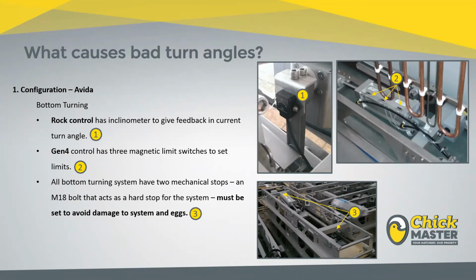If you've got a Gen 4 control, is denoted by picture 2 in the top right corner here, you're going to find yourself with 3 limit switches. Now, these limit switches are magnetic reed switches, which are triggered by a magnetic band that runs down the inside of that actuator. So as that magnetic band travels up and down the shaft of that actuator through the stroke, it triggers those reed switches and lets the control know exactly where in that turn system we are.